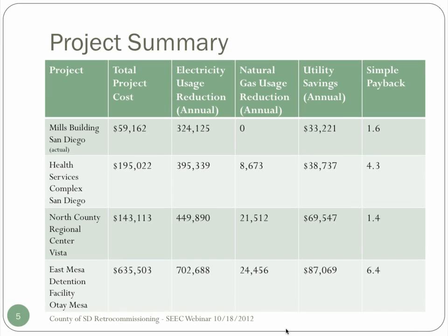Our air handling units, we went through and started trending those. We noticed that the VAVs were not backing off properly. It resulted in finding out that the actual VAV box controllers were outdated and not really working properly, so we replaced those box controllers as well as implemented a static pressure reset programming to have those variable speed drives modulate like they should.